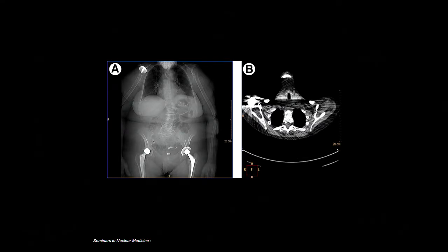Only the high energy streaks of the CT image overshadow all the other photons. When you take an image of one projection you get a lot of noise. When you reconstruct it together, this noise gets amplified, and finally it makes a big noise issue called the streak artifact.